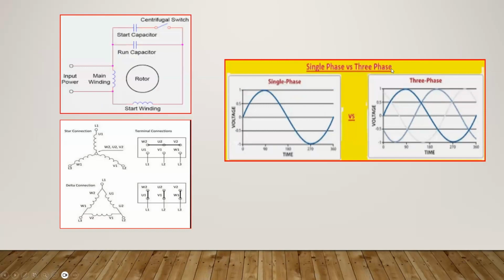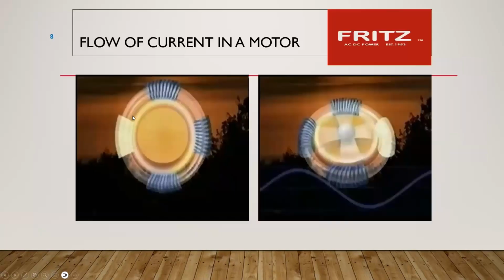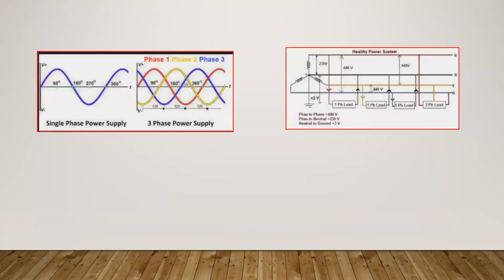So in order to make a single phase motor work, they have a main winding, which basically runs off of the sine wave. But in order to get it to start, they always have these start capacitors. And literally what they're doing is they're building 2 phases of power. Back to our drawing here, to get the motor to start, they have another set of windings in here.